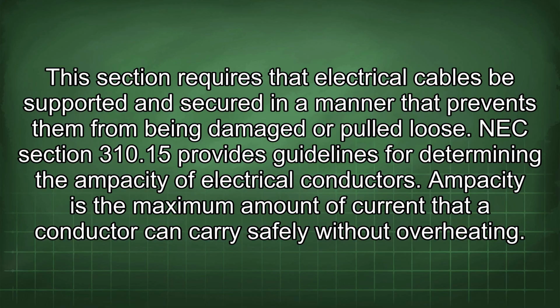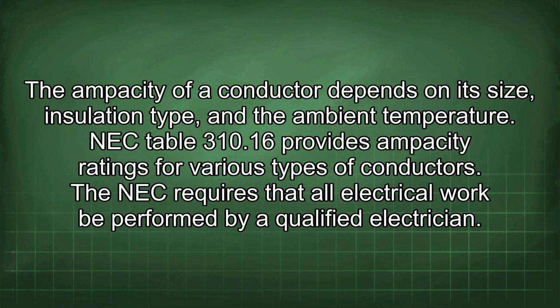NEC Section 310.15 provides guidelines for determining the ampacity of electrical conductors. Ampacity is the maximum amount of current that a conductor can carry safely without overheating. The ampacity of a conductor depends on its size, insulation type, and the ambient temperature. NEC Table 310.16 provides ampacity ratings for various types of conductors.